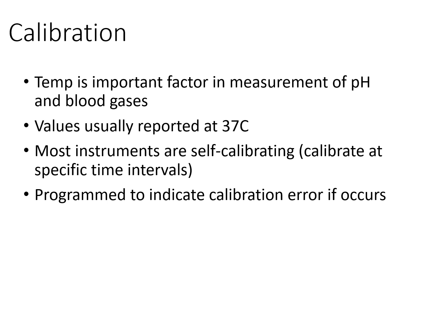Instrument calibration: most modern blood gas analyzers and pH meters are going to be self-calibrating. These instruments perform calibration at specific time intervals automatically, which helps to ensure consistency and accuracy. Calibration is performed using standard reference solutions or gases to maintain measurement reliability.